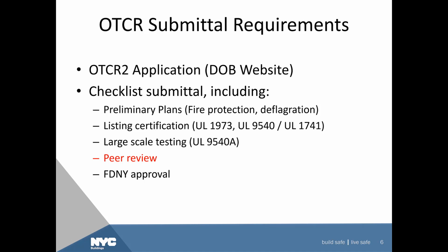All key stakeholders get a sense of how the battery performs under certain conditions, such as an overcharge condition that would create a thermal runaway event, or a condition for the buildup of explosive gases. This test identifies how the batteries will perform under these conditions. So that is a requirement.